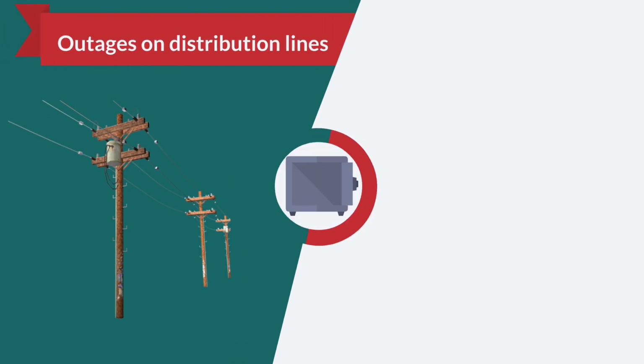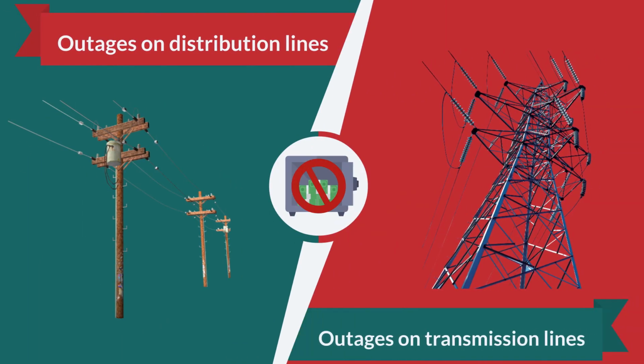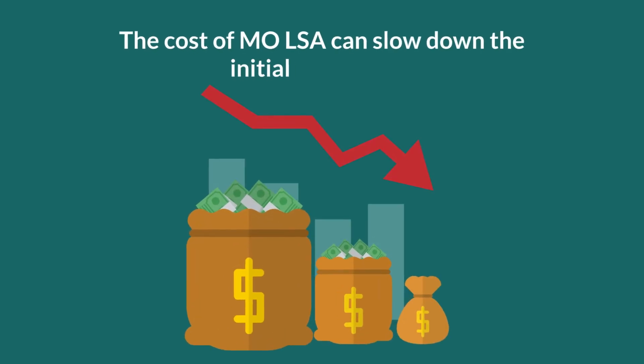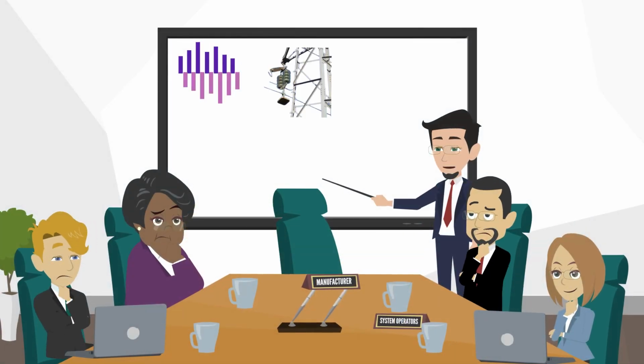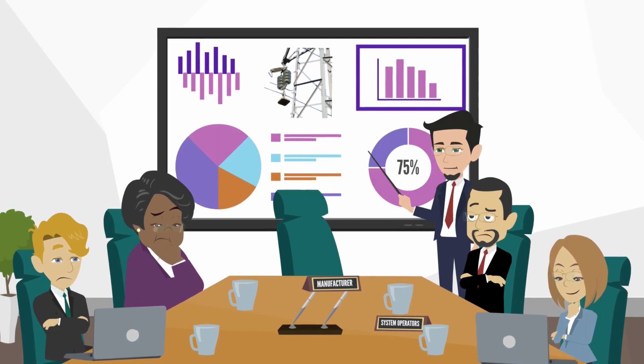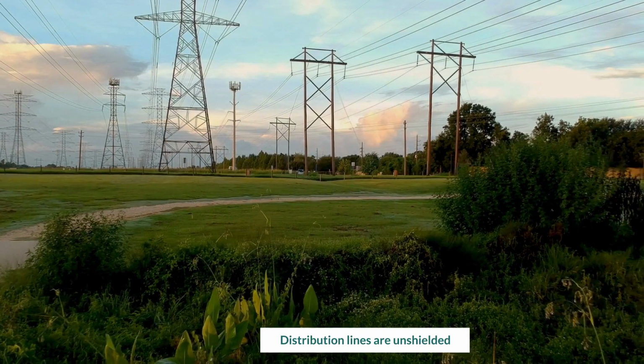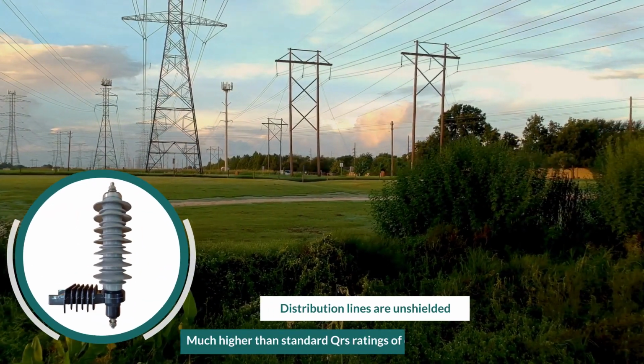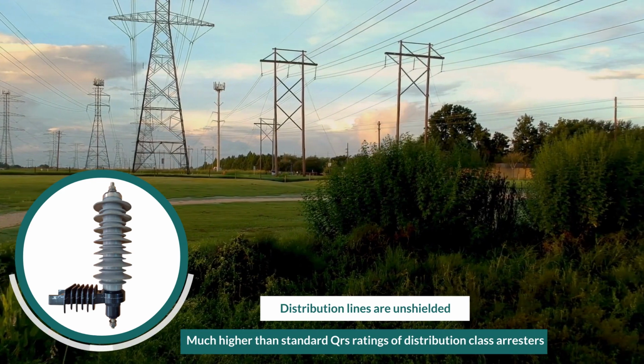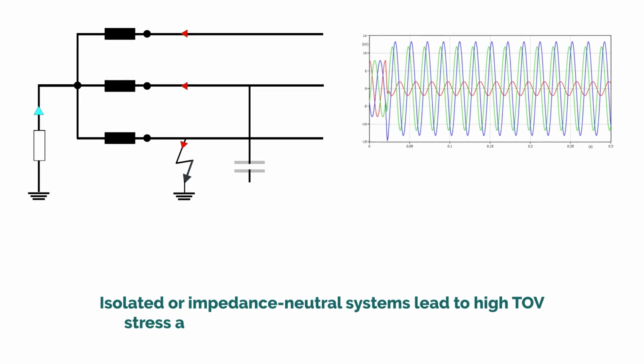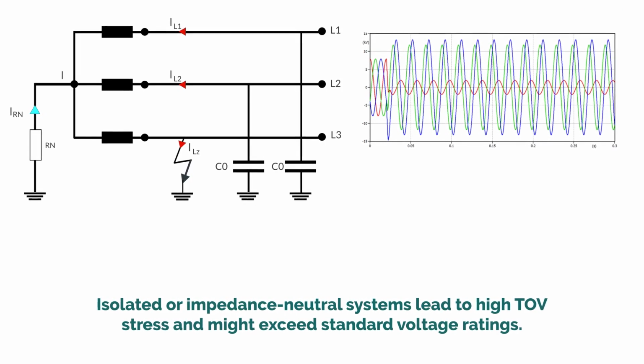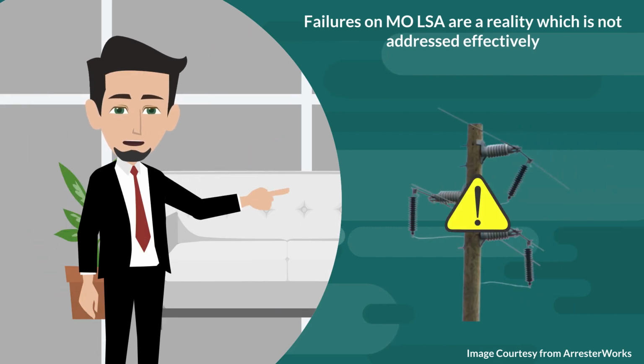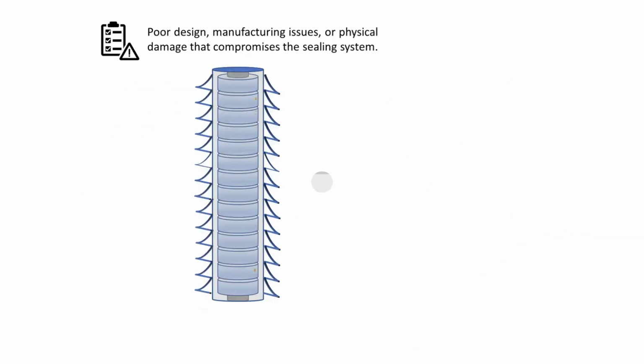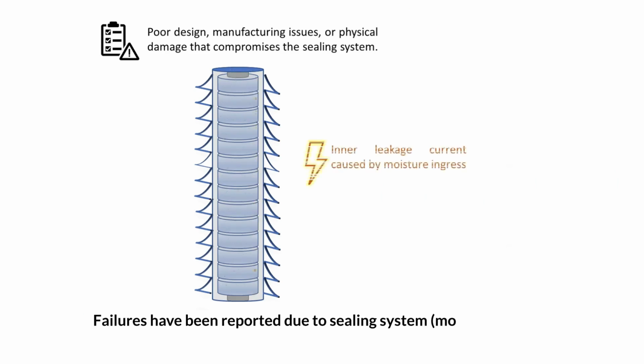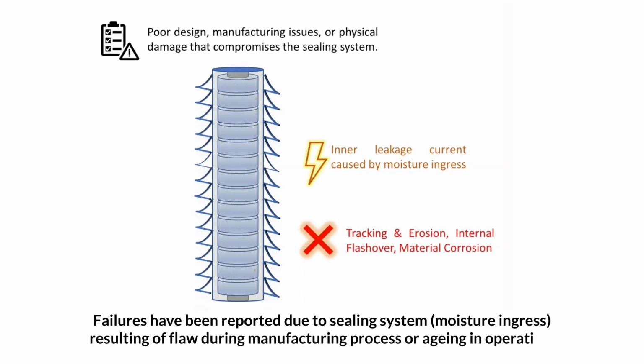Outages on distribution lines are not so financially critical as on transmission lines. The cost of MOLSA can slow down the initial investment. Indeed, the solutions and the experience of the manufacturers are often not very convincing for the system operators. Since most of the distribution lines are unshielded, the expected lightning charge transfer is much higher than standard ratings of distribution class arresters. Isolated or impedance-neutral systems lead to high TOV stress and might exceed standard voltage ratings. Failures on MOLSA are a reality that is not addressed effectively. Failures have been reported due to sealing systems, moisture ingress resulting from flaws during the manufacturing process, or aging in operation.